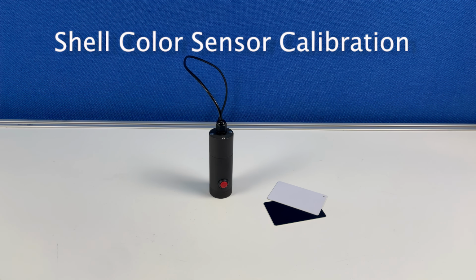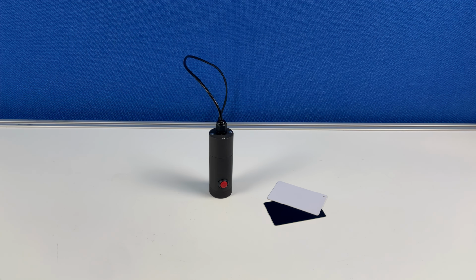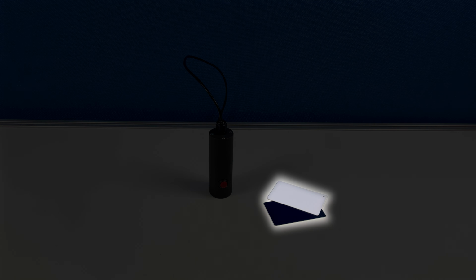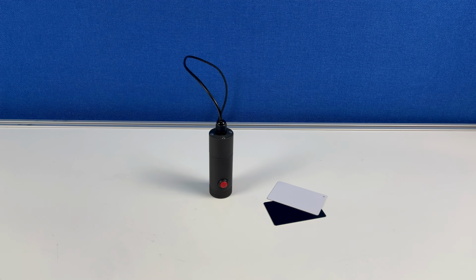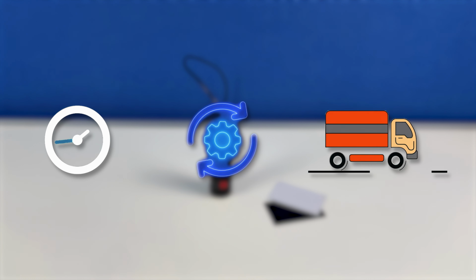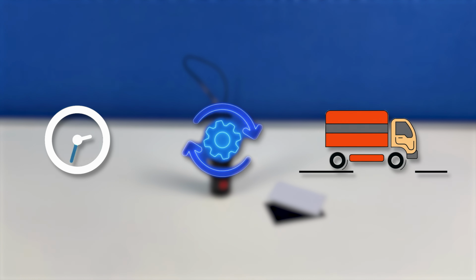In this video, we'll walk you through how to properly calibrate your shell color sensor to ensure accurate and consistent measurement results. Before you begin, make sure you have your shell color sensor as well as the black and white calibration cards ready. For accurate results, the shell color sensor should be calibrated at least monthly, after a software update, and whenever the device has been transported, relocated, or serviced.